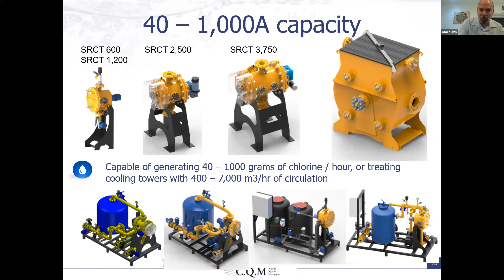This system is so robust, reliable, and strong, and can handle hard conditions, that we applied it to many other directions. This is a cooling tower treatment system model that uses brine. You have one brine tank here, and here one circulation tank, and in this tank we can produce a very strong and stable reservoir of chlorine for whatever need there is. This is basically the heart of the system, which is what you see here.